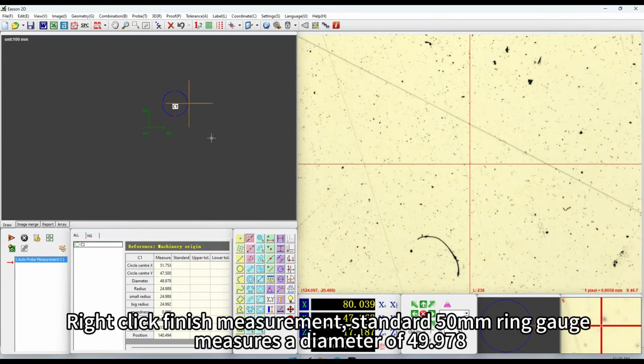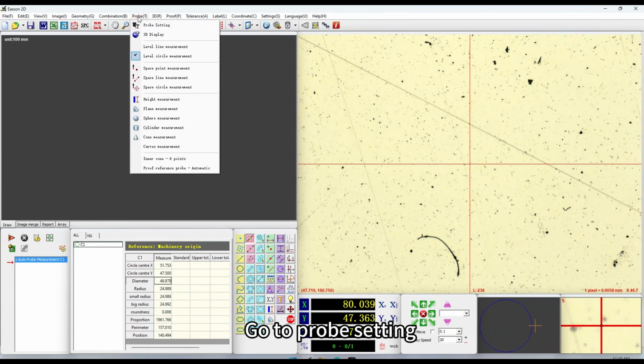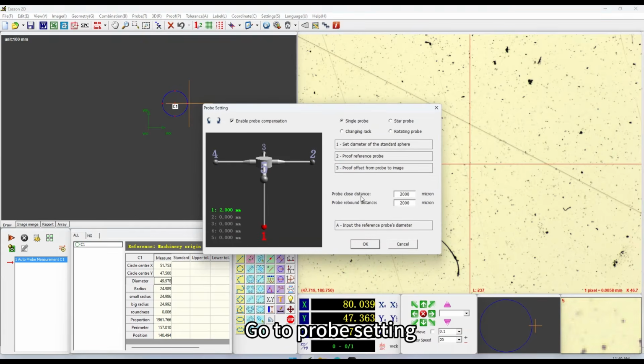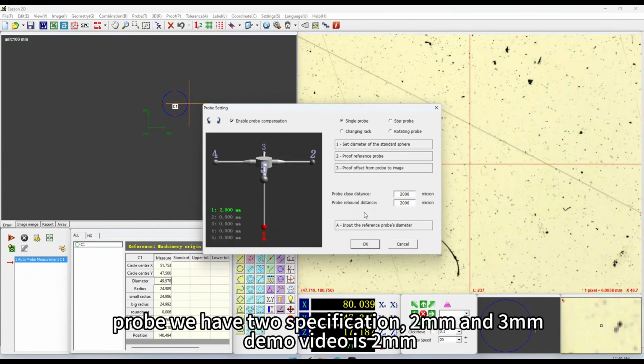Right-click Finish Measurement. The standard 50 mm ring gauge measures a diameter of 49.978. Go to Probe Setting. We have 2 probe specifications, 2 mm and 3 mm. The demo video uses 2 mm.